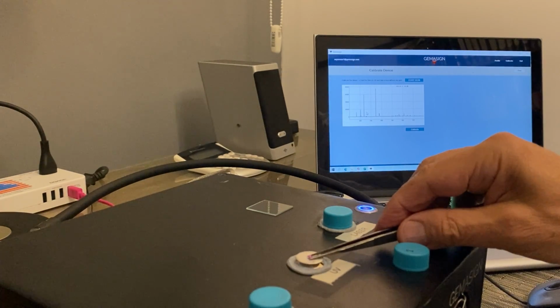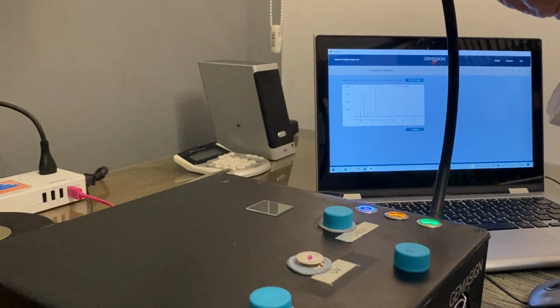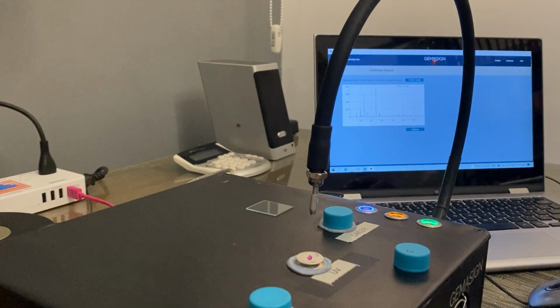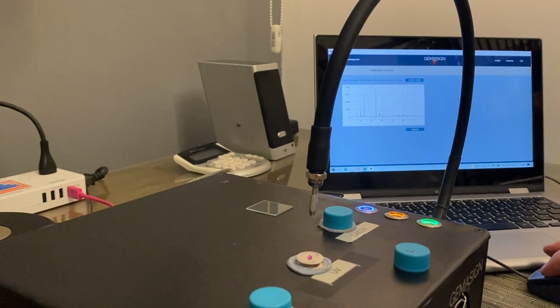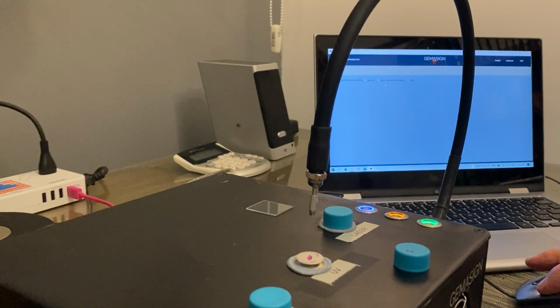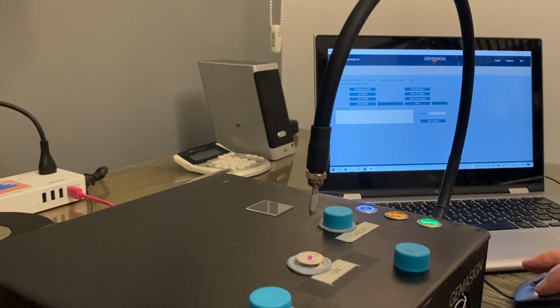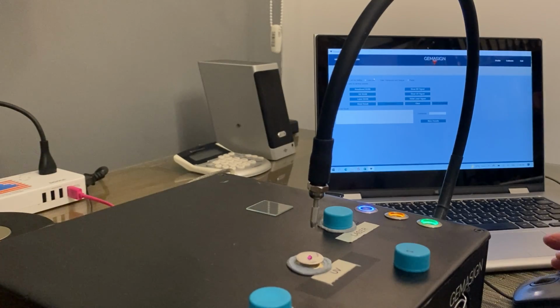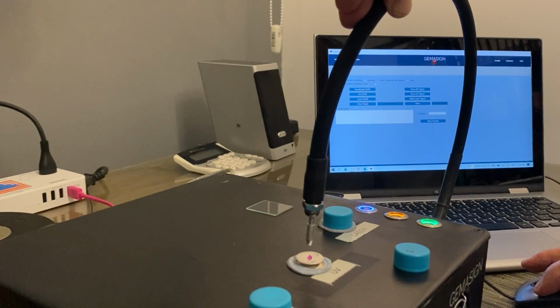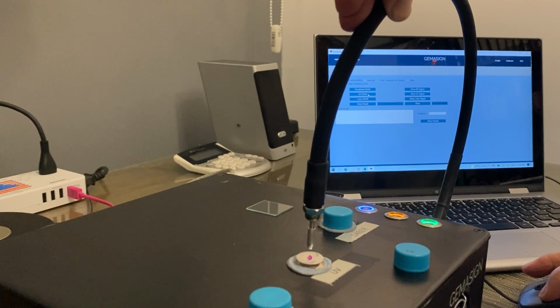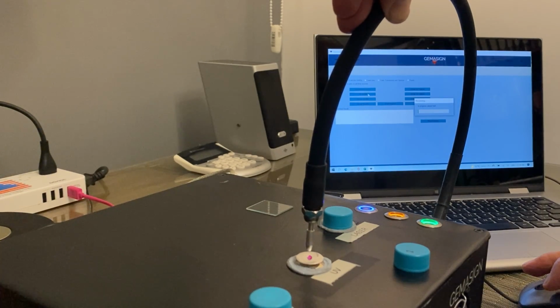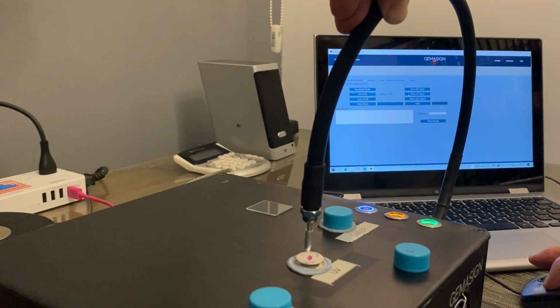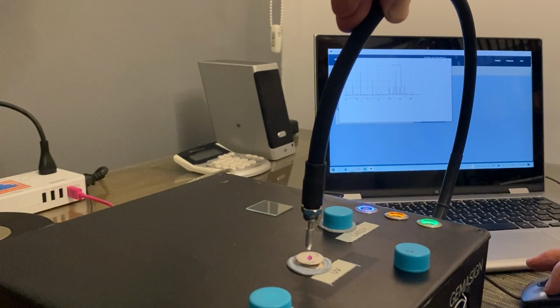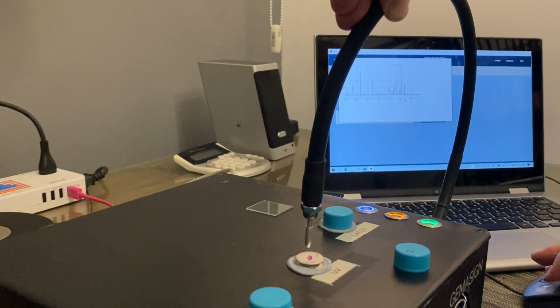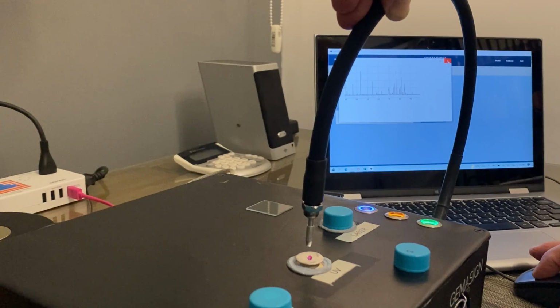All right, so what I'm going to do now that we have the calibration done, I'll put a little stone in here. I'll bring back out my fiber optic. I'll close out the calibration from the screen. And this is my regular sample. So if I go back in here to do an analysis, okay, I can do that. Let me see if I can do it like that. And go to the UV. Okay, it's captured it. And that's the UV spectra from this particular stone, which happens to be a ruby. Okay, so that's that one.